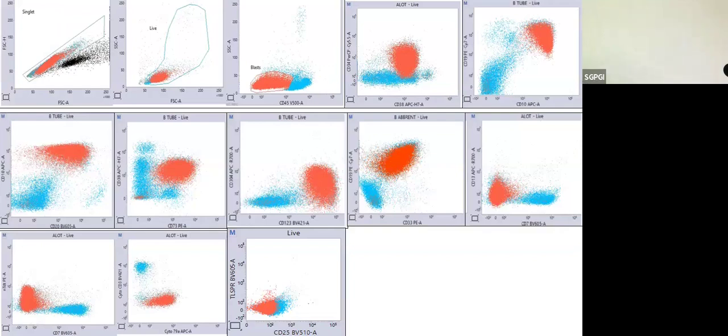So when we look at the flow cytometric plot, the first plot usually is the time gated plot that exactly tells you how stable your machine was during acquisition. If there is any blockage or something during acquisition, you get a gap in the time. Based on that, the next plot is FSC area versus FSC height.